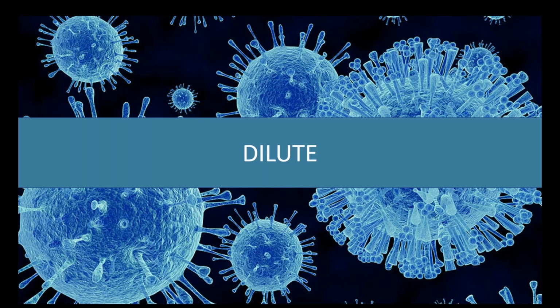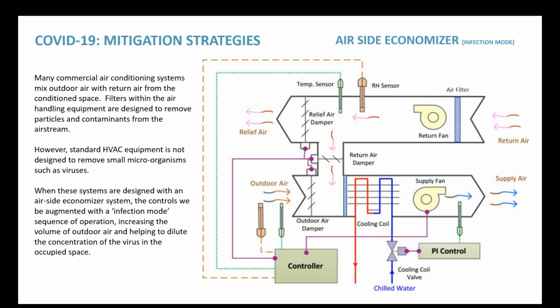So now let's talk about some dilution strategies. While it's a little bit out of order, this is where we like to start in some cases, to look at how much outside air we can bring into the space. The example we have on screen here is what we call the infection mode for an air handling unit that has an outside air economizer. Generally the idea is bring in as much outside air as possible to the occupied space to dilute any contaminants that may be in that space. Increasing at least to the minimum code required outside air is ASHRAE's recommendation, but they also recommend that you take it a step further and try to increase outside air. Well, how can we do that?